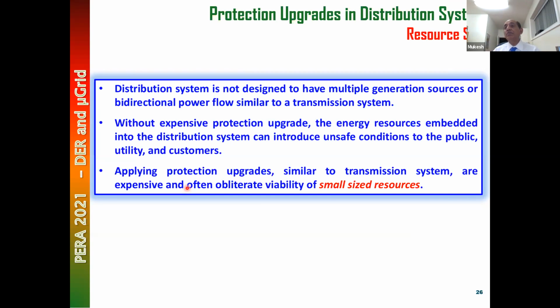But if you apply transmission system protection, which is very expensive, to the distribution system, you will kill the viability of the distribution resources. So that's not going to work. That's going to kill the distribution resource. But if you do nothing, that's an unsafe condition. You cannot have a fault and not detect it. So the point I'm making is that applying a protection upgrade similar to the transmission system is very expensive, but not doing anything is unsafe. So what do we do?